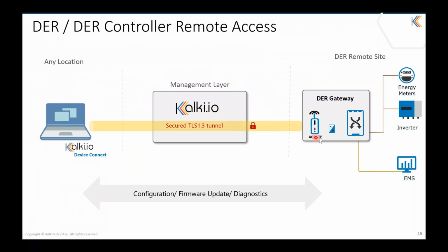And this certificate can be controlled. You control the validity of the certificate. You can have the validity window in such a way that you can access the devices only from maybe tomorrow 5 to 10 p.m. So you can issue the certificate for that particular window, and any user coming with the certificate will be allowed to access those devices or assets only in that particular window.